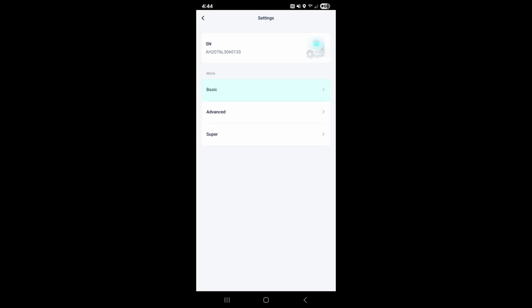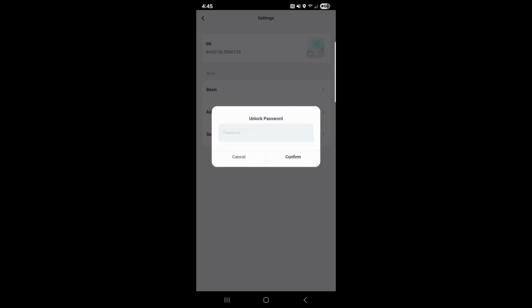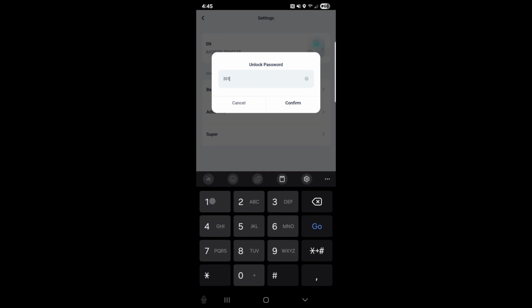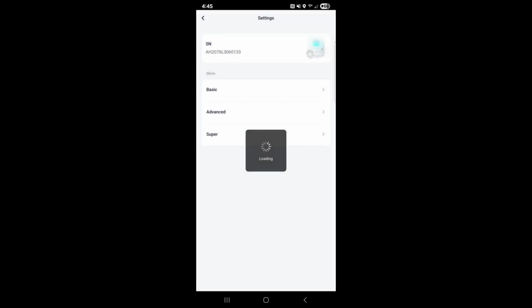Start with basic settings to verify the date, time, and language are correct. Select System Switch and set this to on, then press Save. Select Work Mode and choose your desired mode appropriate for the system owner, then press Save. Go back to the inverter settings and enter the advanced settings. Input the password found in the commissioning guide to access advanced settings.